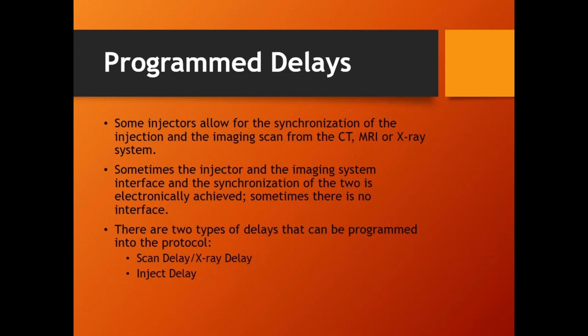Now scan delay, let's talk about that. That's for CT scanners and MRI scanners, right? It's the exact opposite. I want the injector to start injecting, and so many seconds later, I want the imaging system to start doing its thing, whether it's CT or MRI, right? They don't use scan delay very much. It's typically the opposite. Typically, they get the patient rolling, then they start injecting fluid in the region of the patient.